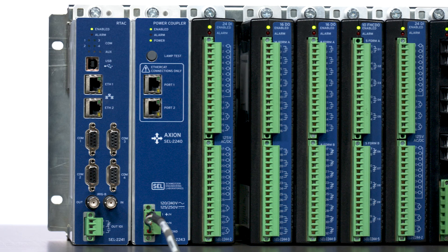The Axion backplane I'm using today includes an SEL 2241 R-TAC, a power coupler, and various input and output modules commonly used in bay control applications. The first thing we'll go over is how to create custom screens using the Axion R-TAC and the integrated base screen builder software.